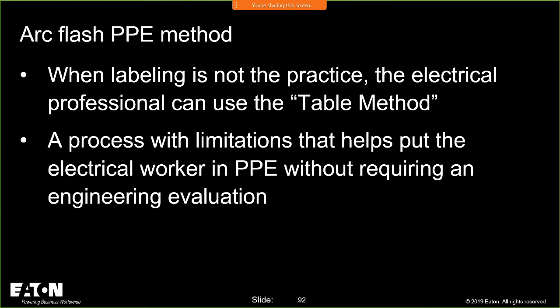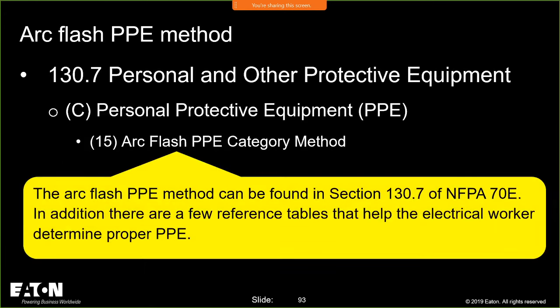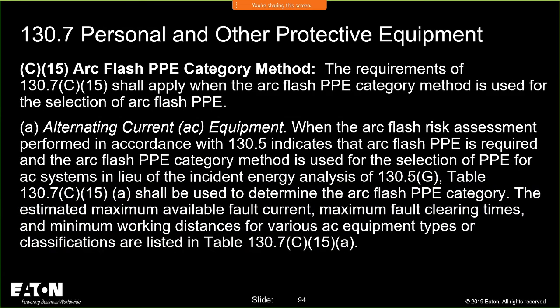It's a process that your journeyman and others are going to use to determine the personal protective equipment. That's why it is in Article 130 of 70E, personal and other protective equipment. The arc flash PPE category method is what it's called. Now, this is a busy slide. I'm not going to dwell on it, but it talks about when it applies, that the arc flash risk assessment is performed in accordance with 130.5, and all this other good stuff.